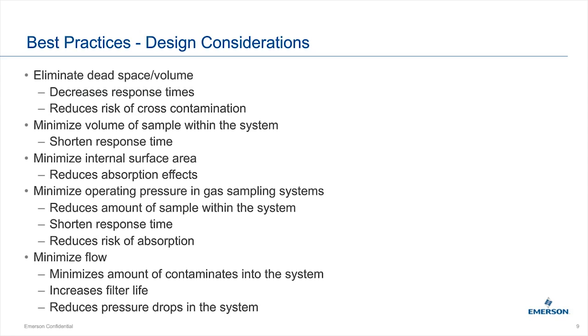Minimize the volume of sample within the system — the more volume, the longer it takes to get through the system, so minimizing it shortens response time. Minimize internal surface area: larger surface area increases the possibility of absorption or interaction between the tubing and your sample, so always use the smallest tubing possible. Minimize operating pressure in gas systems — lower pressure means lower volume, which reduces lag time and improves response. Note: for liquid systems, you do not want to minimize pressure; you want to maintain or increase it.